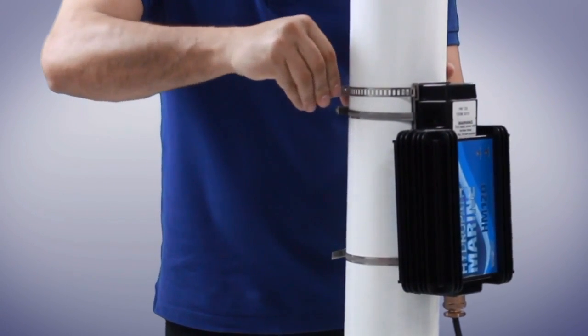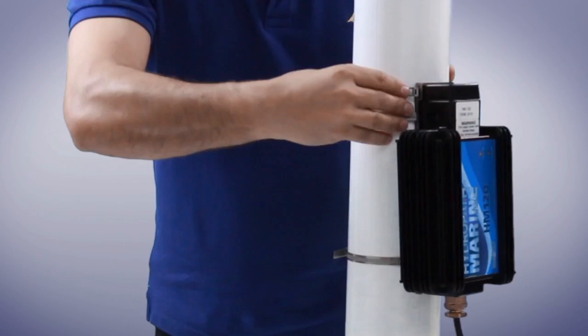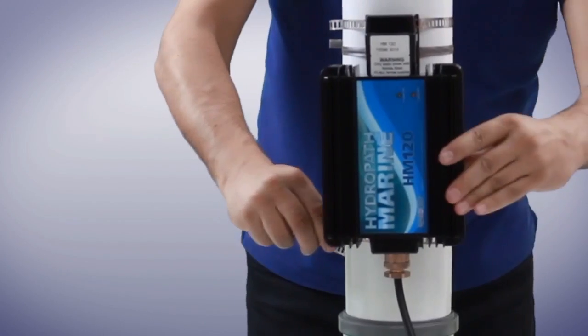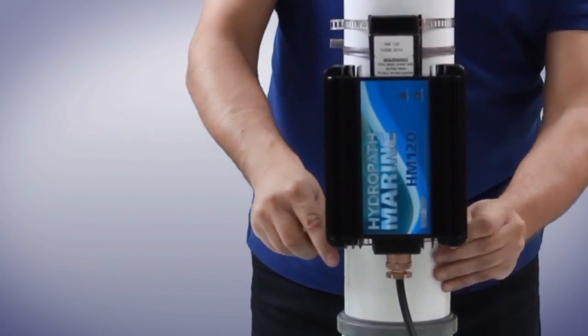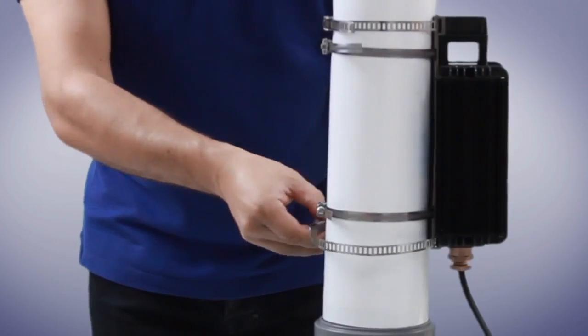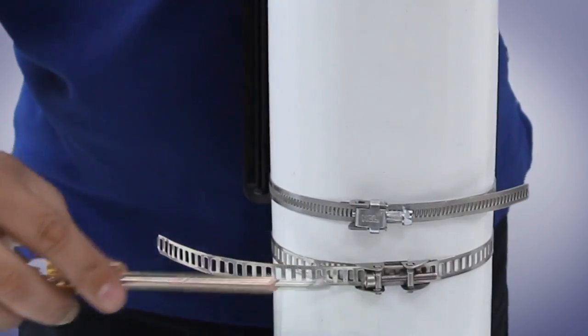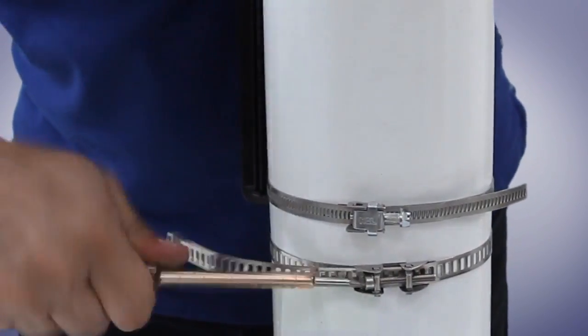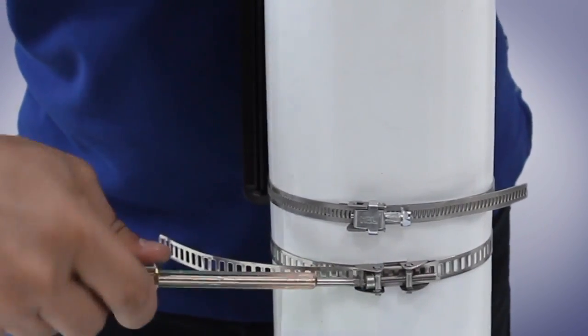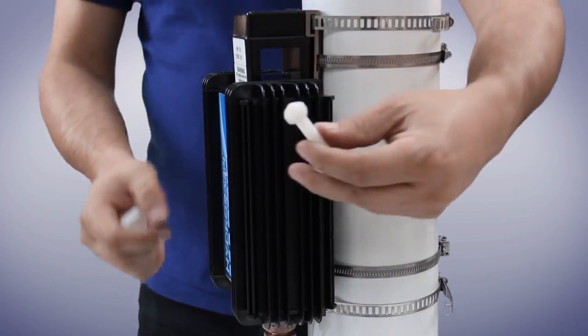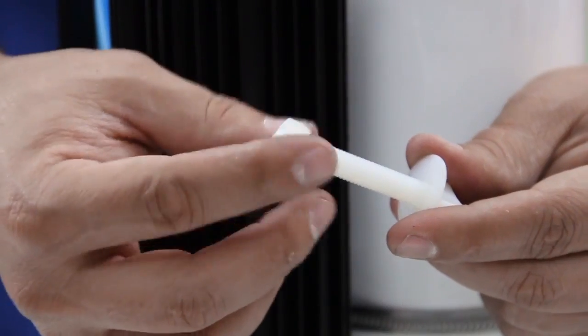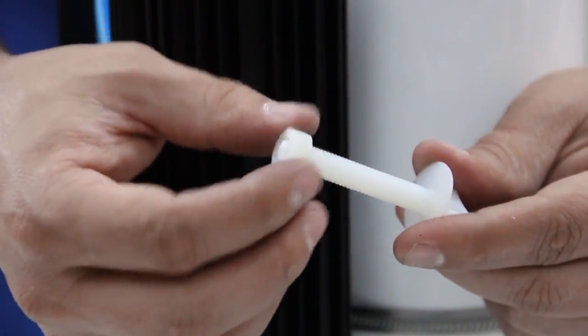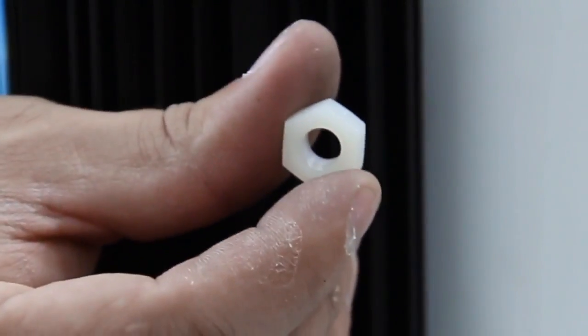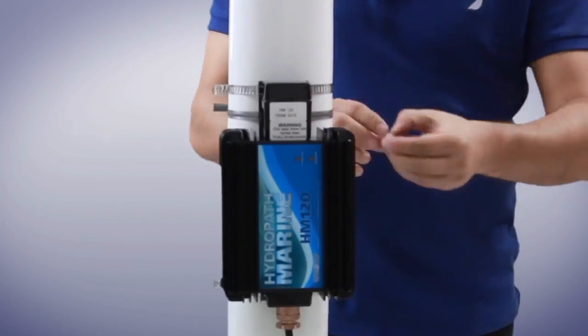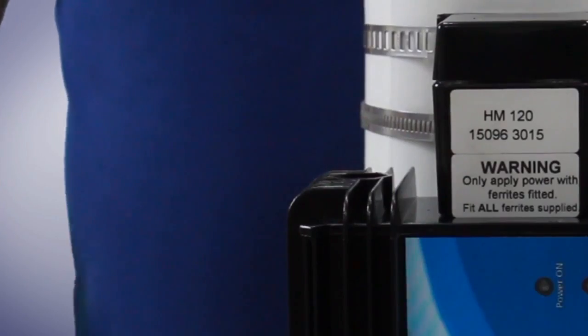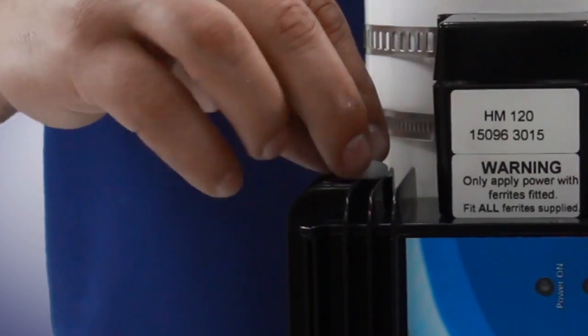Fold in the excess band. Repeat with the other band. Double-check and fasten again all the bands. Make sure the unit is firmly fastened to the pipe. Take the hexagon nuts and separate them from the screws. Place the hexagon nuts into the holes next to the holding cage.